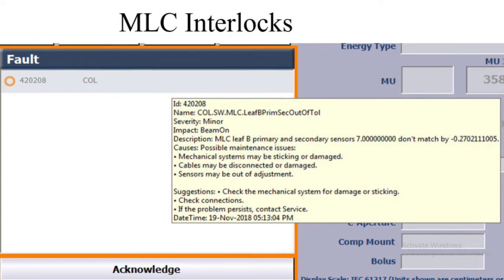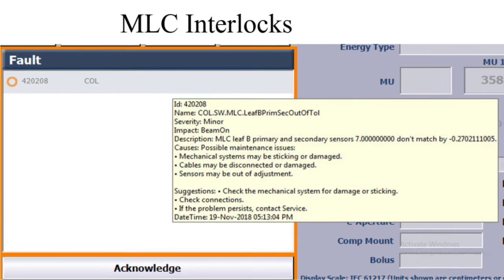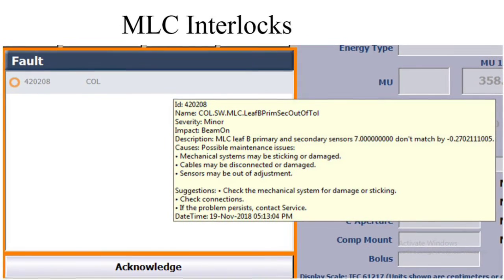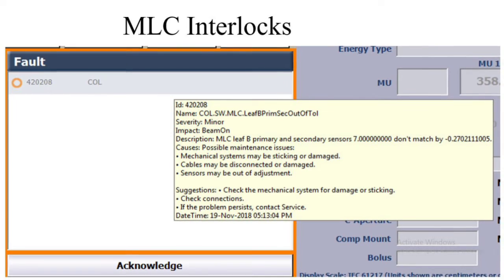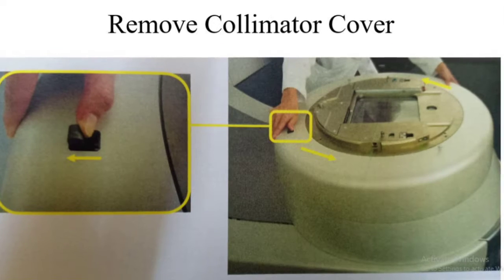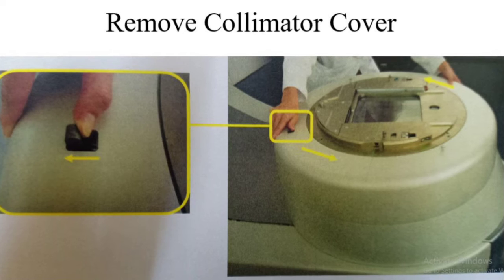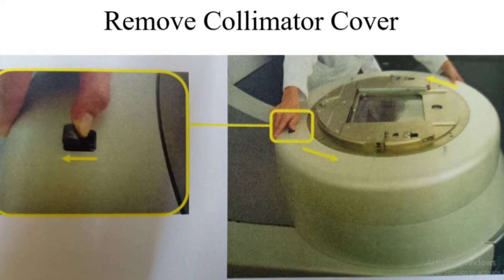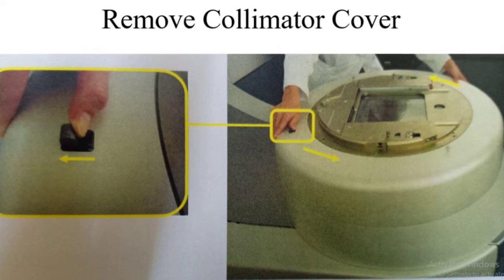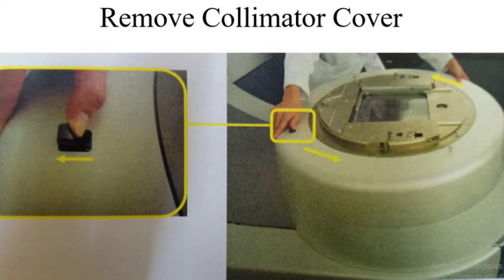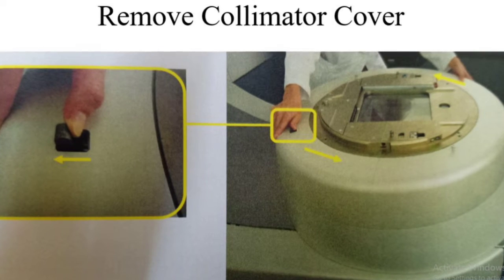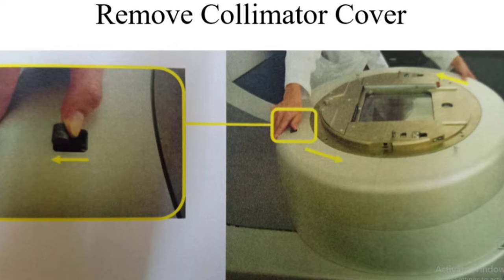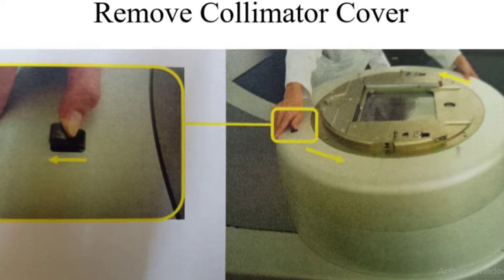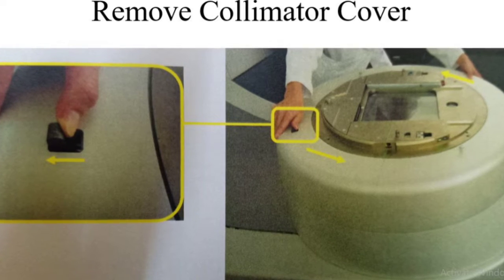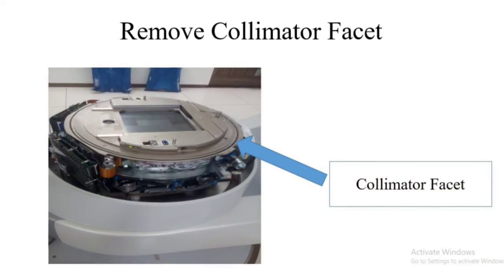Now we shall see what are all the possible actions we as physicists can take related to the MLC interlock. Whenever the interlock comes, the first thing that comes to mind is the MLC motor. But it is not always necessary that the motor needs to be replaced. So one should investigate and find out what the exact issue is. For that, first we have to rotate the gantry to 180 degrees and close the jaws completely, and then remove the collimator cover, and then remove the collimator facet.